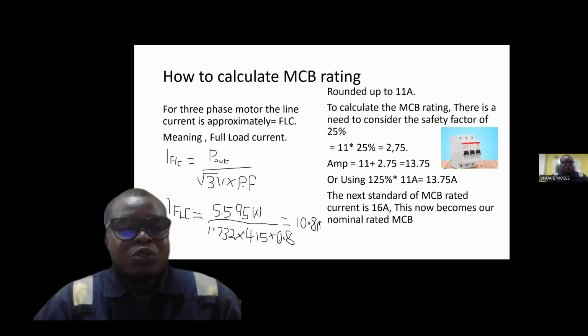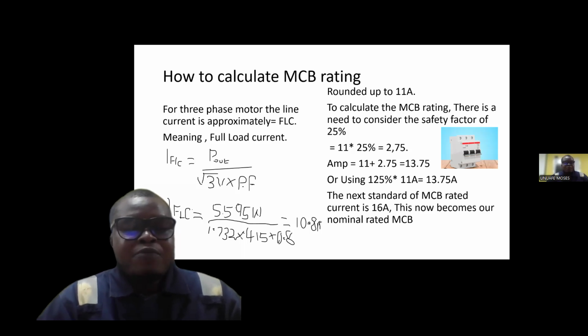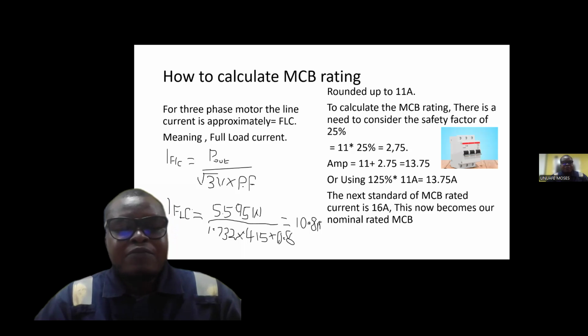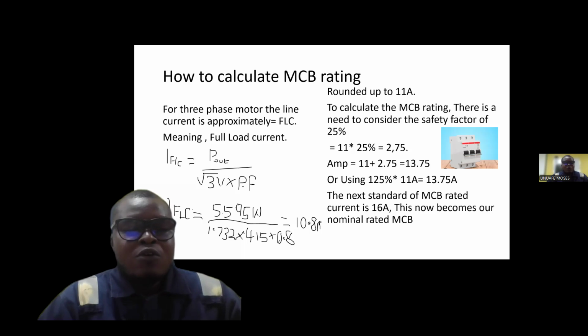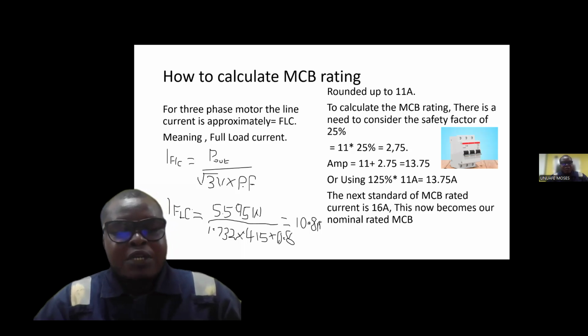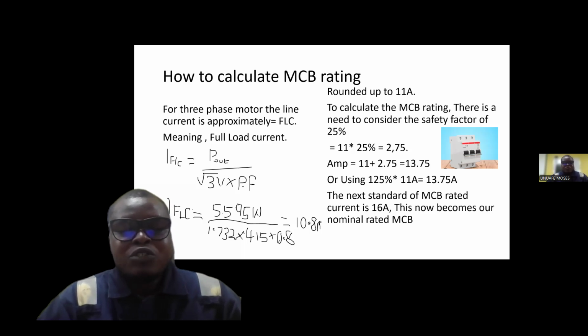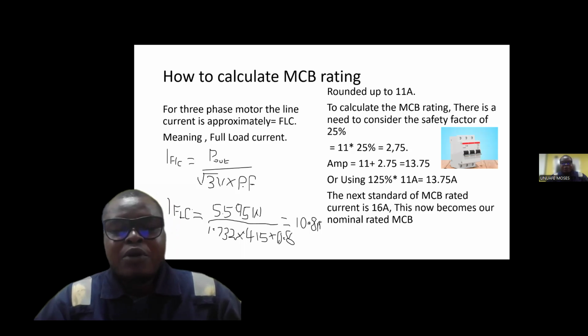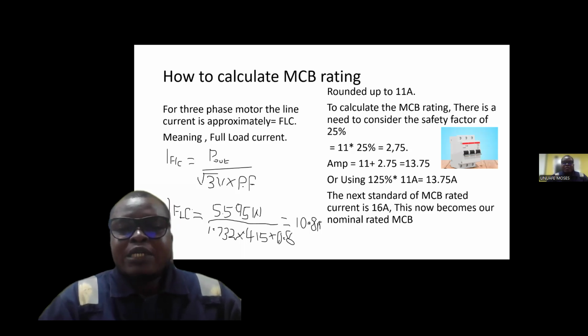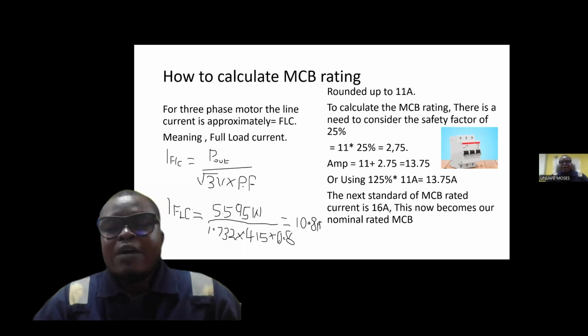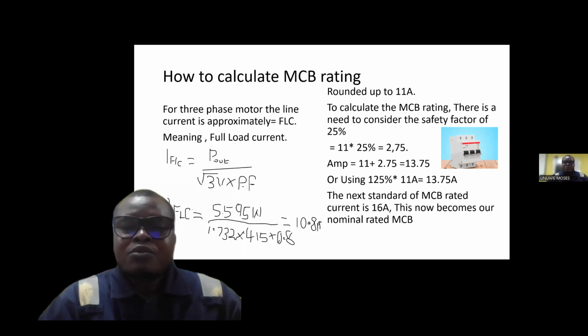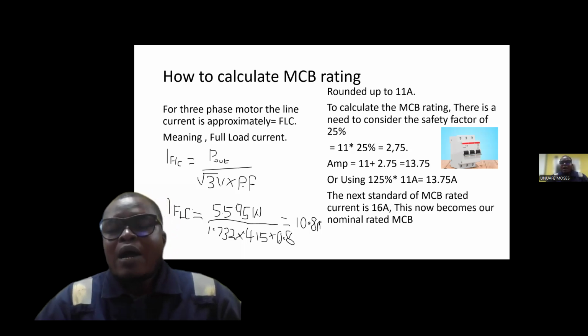And when you substitute the power, which is 5,595, all over the root of 3 multiplied by 415, is going to give you what? 10.8. Approximately, that is giving us what? 11 amps.